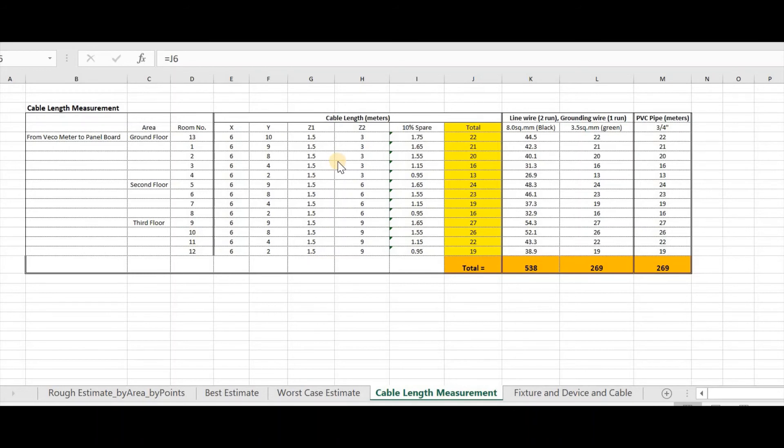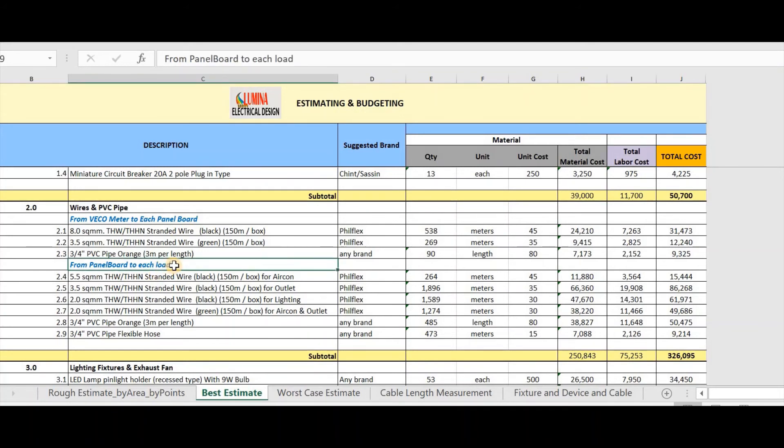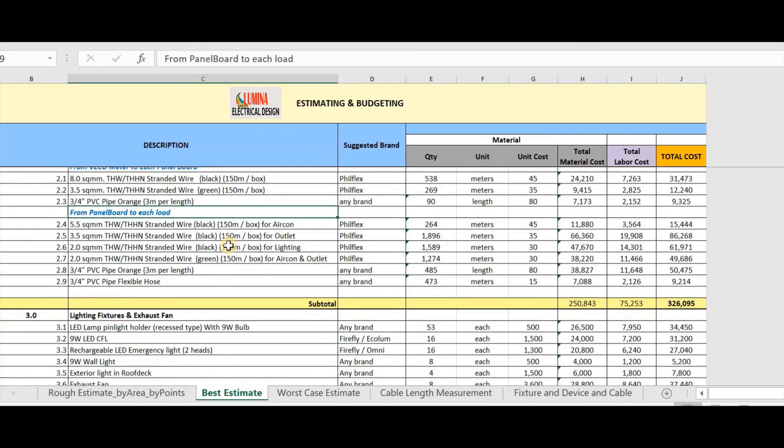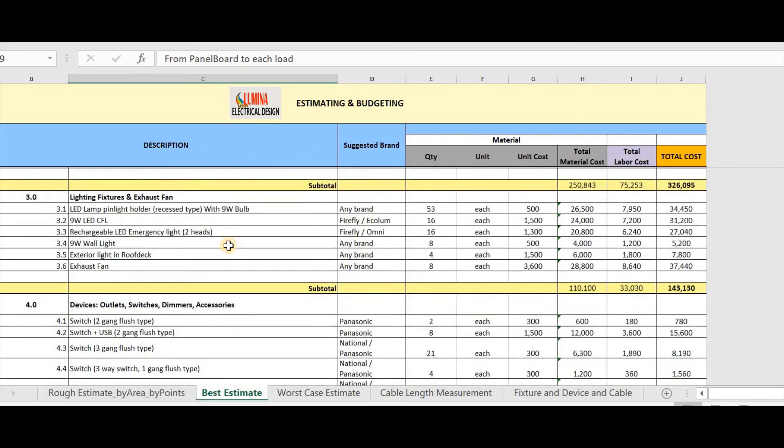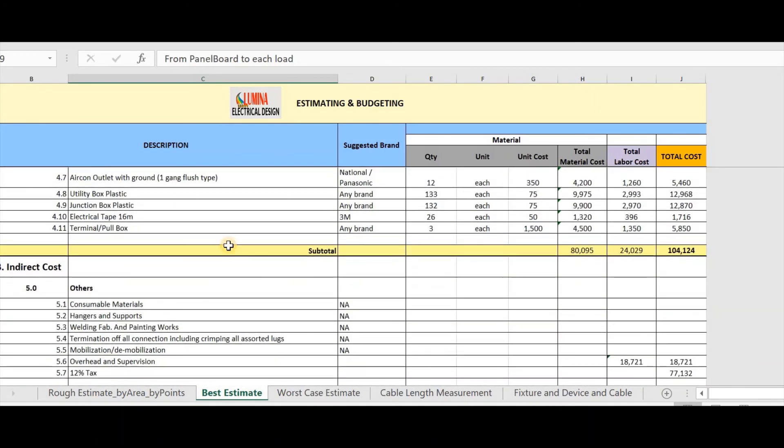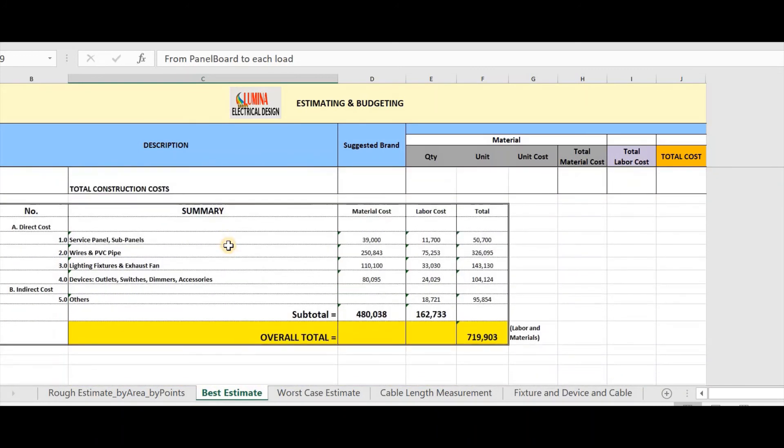Then line wire multiply it by 2 for 2 runs. We have this total. For grounding wire, we have also this total. Then of course, we can also get the length of PVC pipe. So, that's it. The cable length measurement from the VECO Meter going to each panel. Next is the cable length measurement from the panel board to each load. With the same procedure, you can now have an accurate cable or wire length. Once done, you can input it in your total length. Now let's take a look at my bill of quantity. So, that's it for the best estimate.